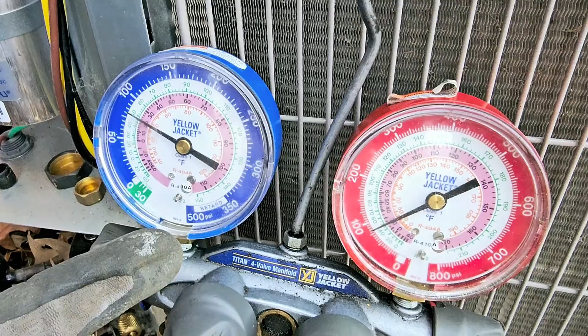Watch the pressures. Once they go to 0, then I'm going to close the suction line service valve. Almost there, 25, 20. And because we don't have a pressure switch, we don't have to jump that out. You know? It's not going to kick the unit off. Almost there. You hear the compressor? Alright, I'm going to go ahead and close it.